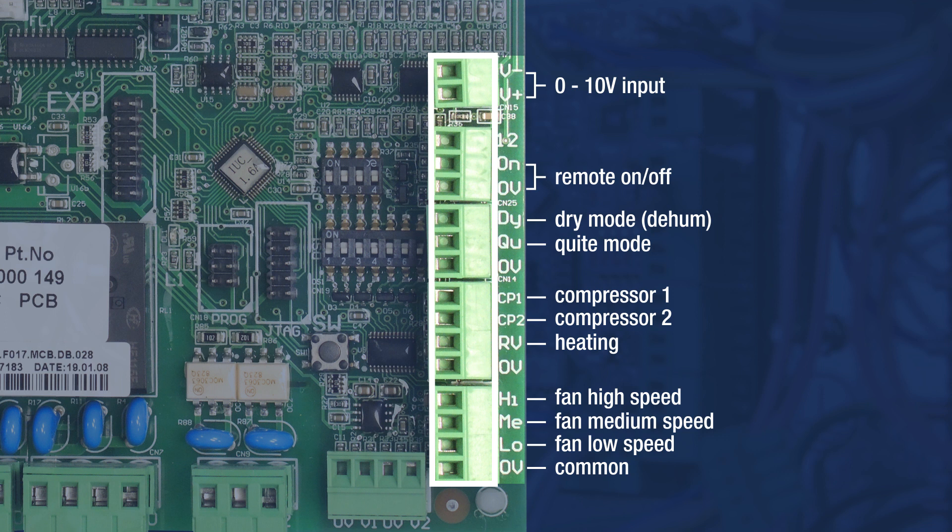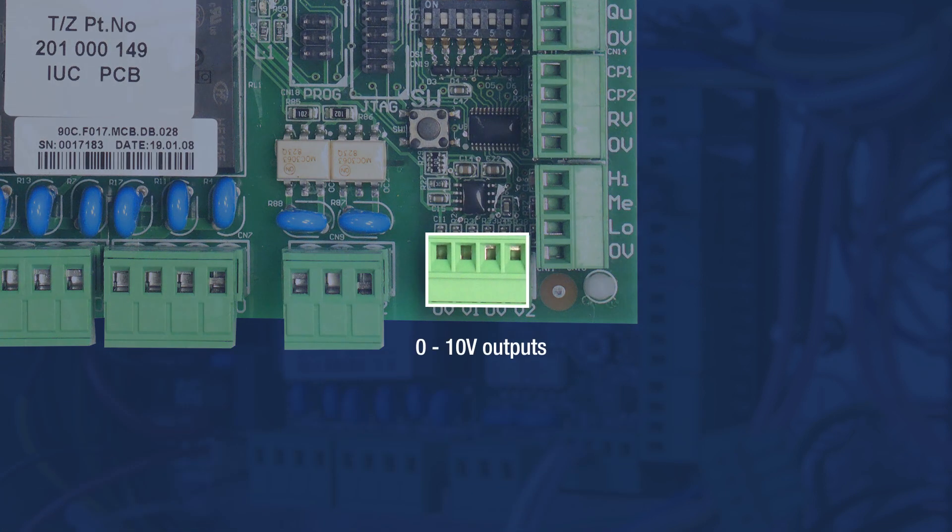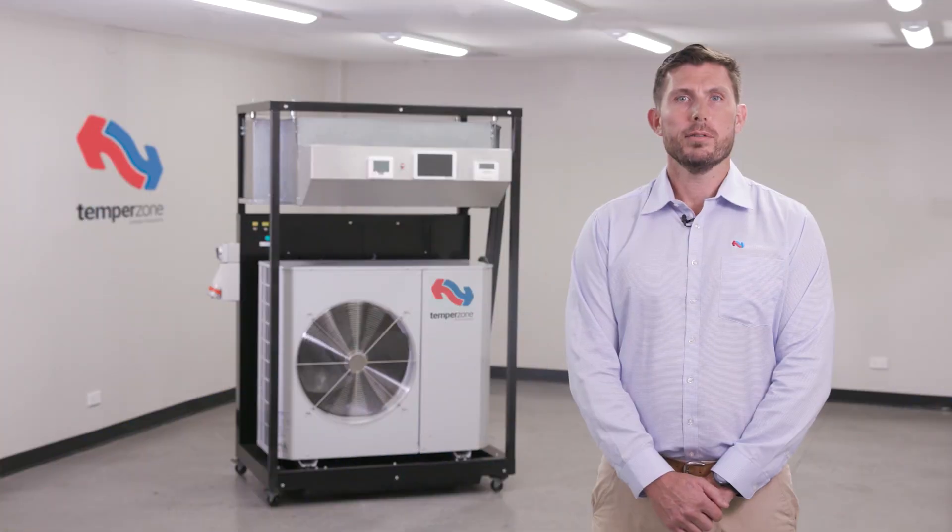A 0-10 volt DC analog input is also provided for compressor speed control. The IUC provides two 0-10 volt outputs on terminals O1 and O2, with terminal 0 volts as the reference for these outputs. Typical uses for these outputs are control of variable speed fans and/or proportional damper position.